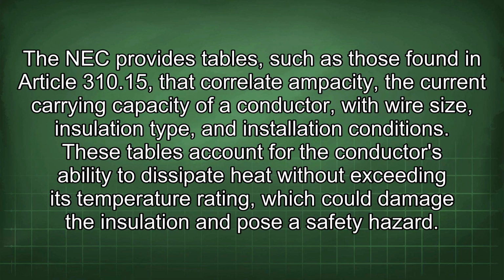The NEC provides tables, such as those found in Article 310.15, that correlate ampacity, the current carrying capacity of a conductor, with wire size, insulation type, and installation conditions. These tables account for the conductor's ability to dissipate heat without exceeding its temperature rating, which could damage the insulation and pose a safety hazard.